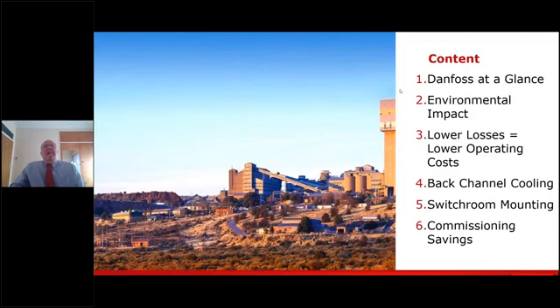And then how the footprint, the actual size of the VSD, can enable a substantial cost reduction in the capital expenditure. And finally, we'll take a look at by using what we call automatic motor adaptation, which is abbreviated as AMA, during commissioning. These labor costs can be reduced, and by optimizing the drive and the motor to run at maximum efficiency, we can therefore save further operating costs.